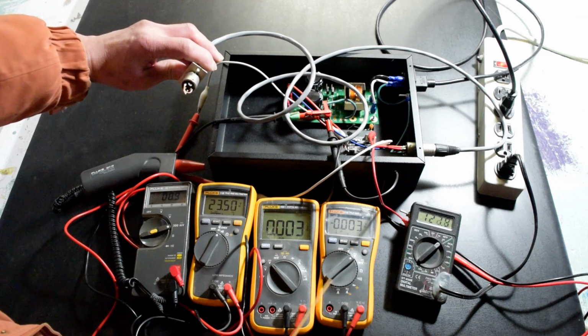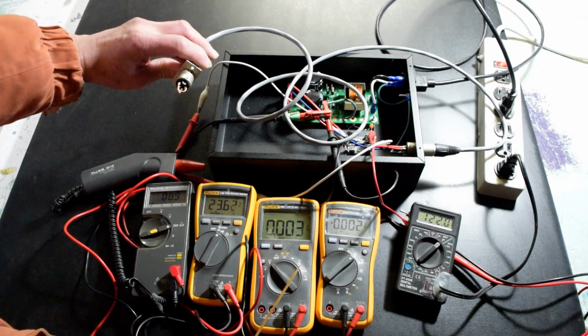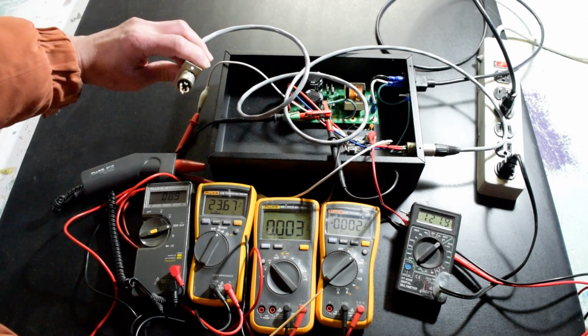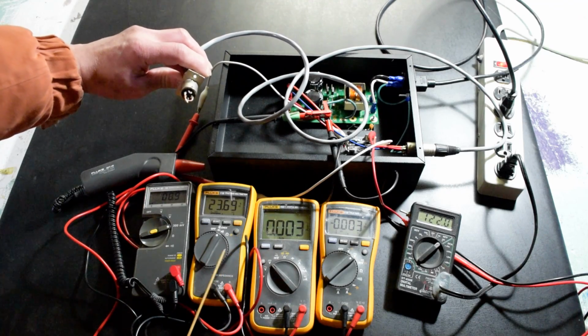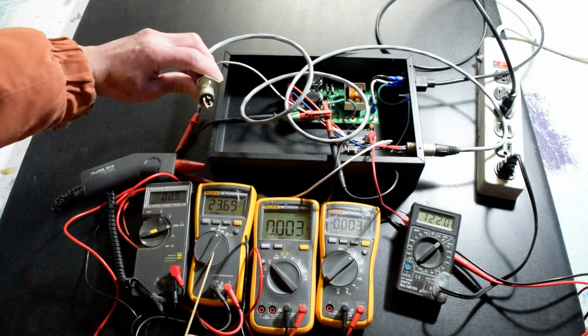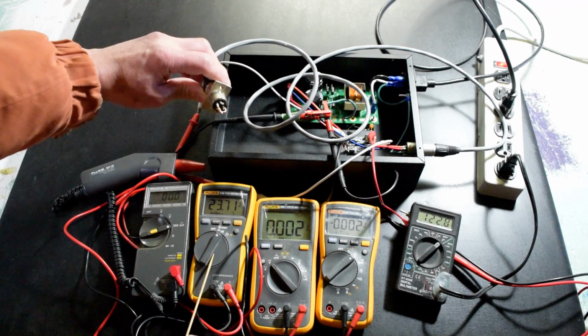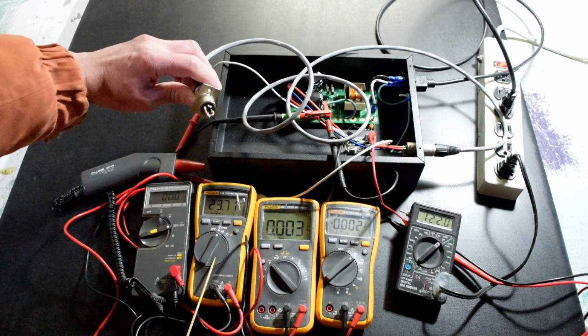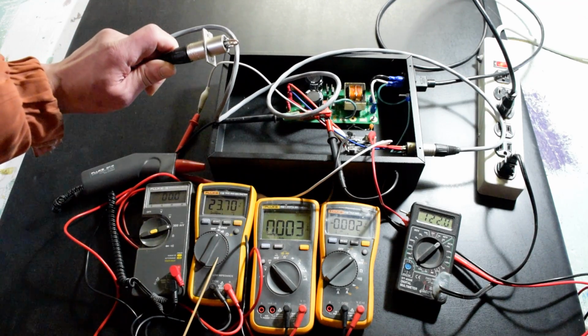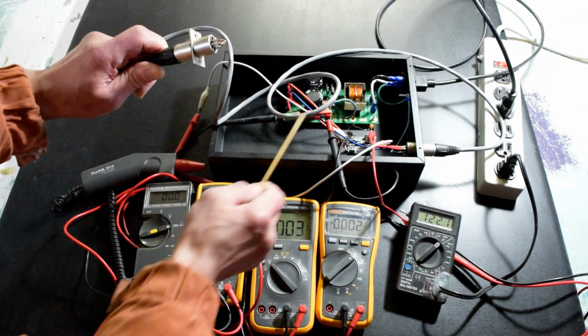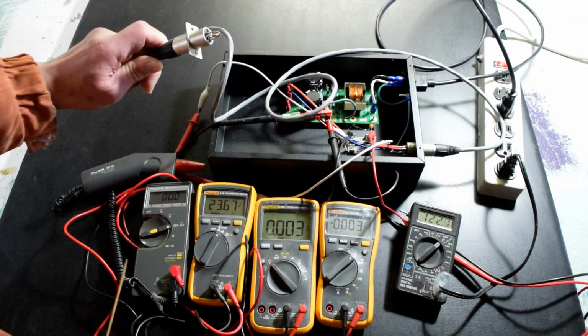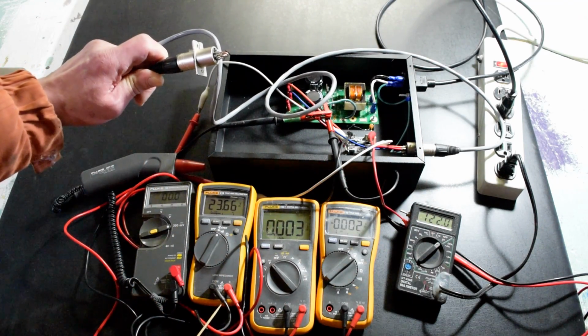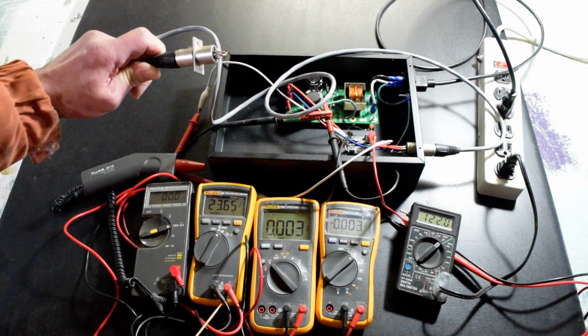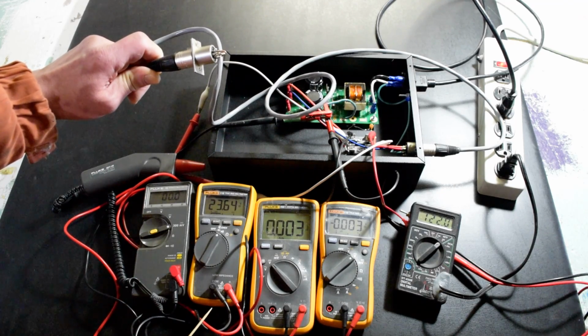These two meters go down to 0 because the resettable fuse is already open, and these meters also indicate there is still voltage before the resettable fuse. Therefore, in this condition, there is no power going through the umbilical cord because the power has been cut off at the resettable fuse location, which is inside the power supply.